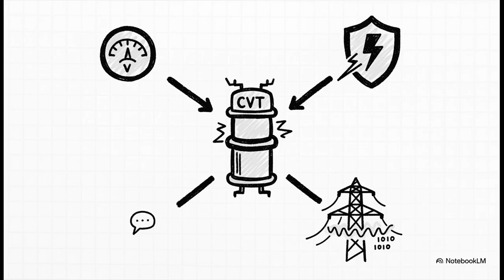And this is where it gets really cool. CVTs can actually inject high-frequency communication signals right onto the main power lines. This lets grid operators send data for remote control, system monitoring, and even voice communication all over the existing grid. So it's a measuring device, a safety device, and a communication hub all rolled into one.